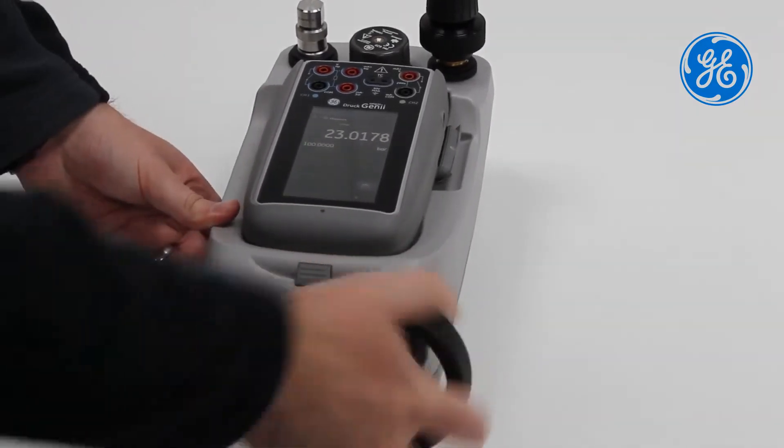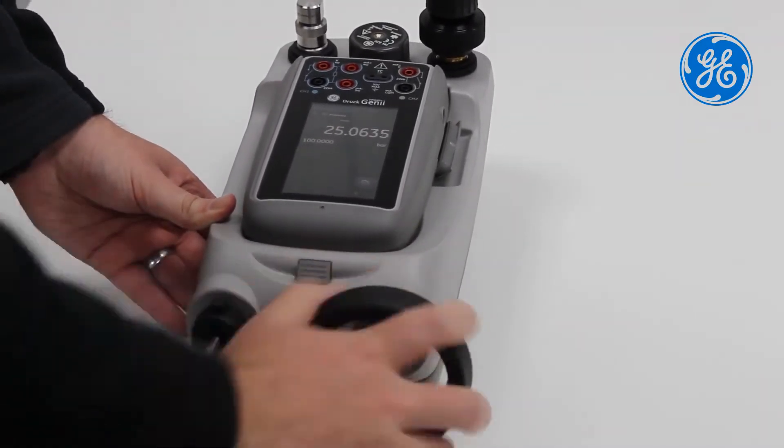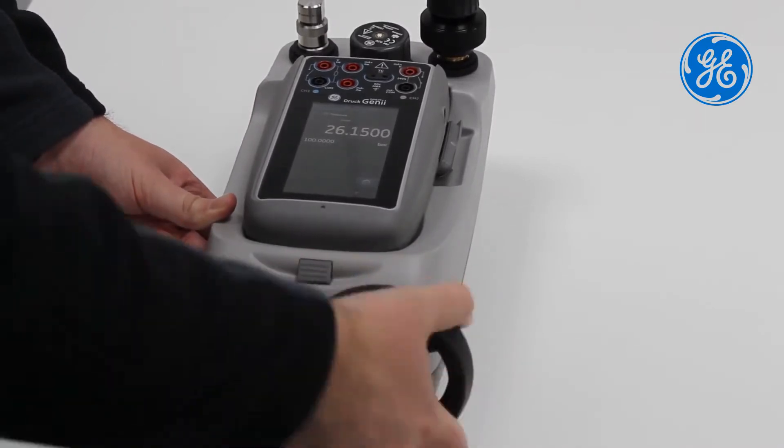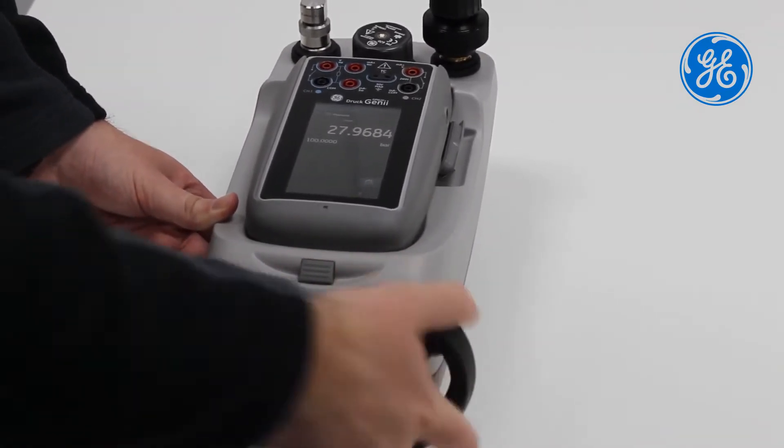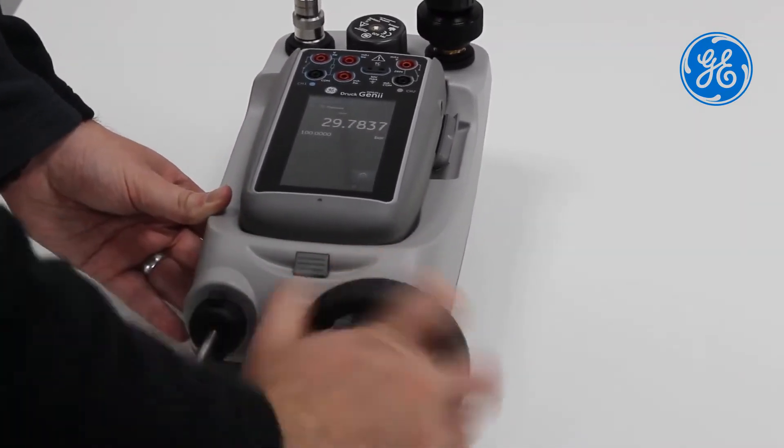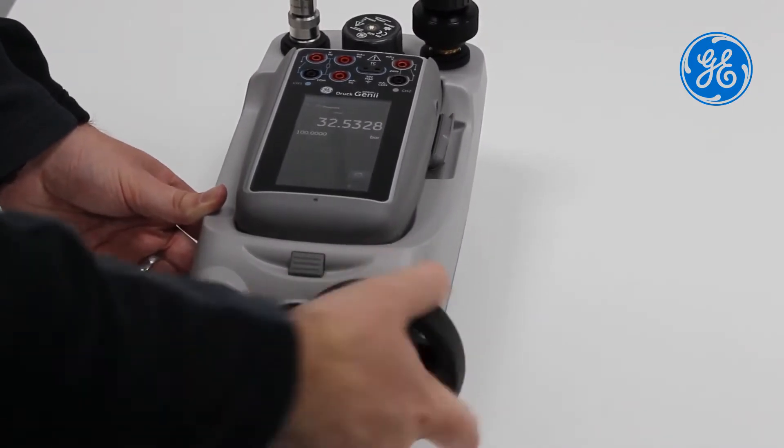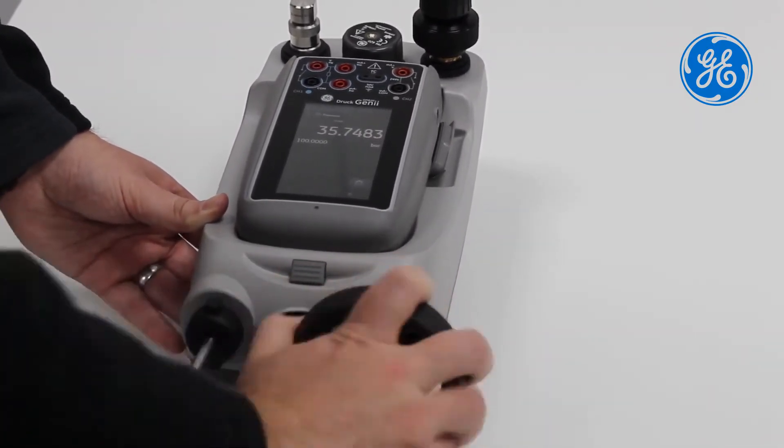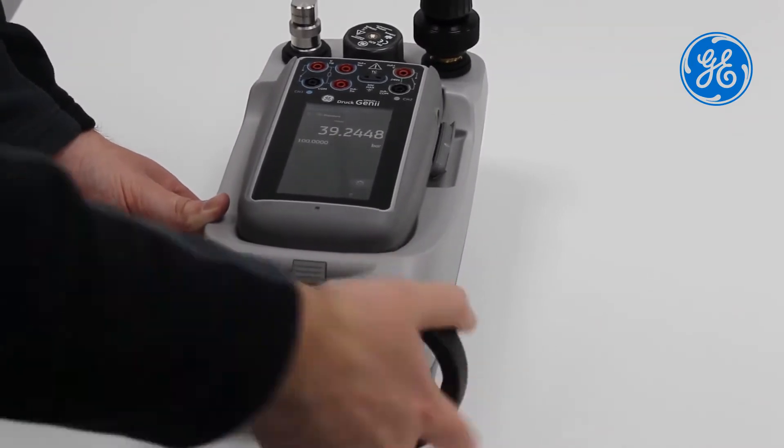There are three pressure generation stations. The PV621, a pneumatic pressure generator for pressures 95% vacuum to 20 bar. The PV622, a pneumatic pressure generator for pressures 95% vacuum to 100 bar. And the PV623, a hydraulic pressure generator for pressures up to 1000 bar.